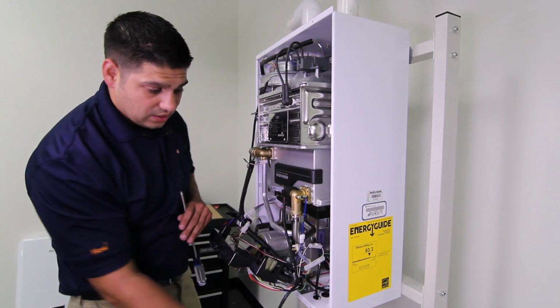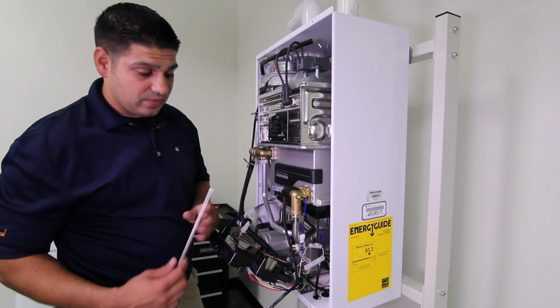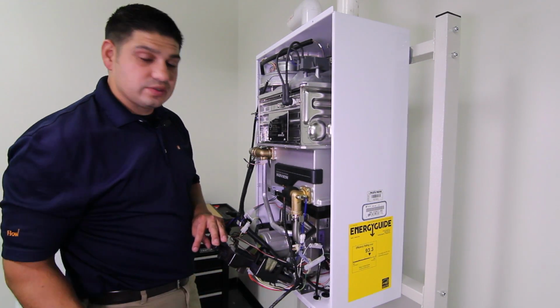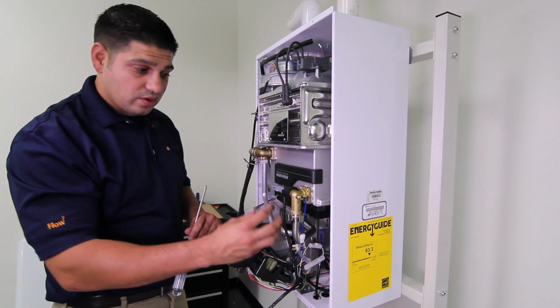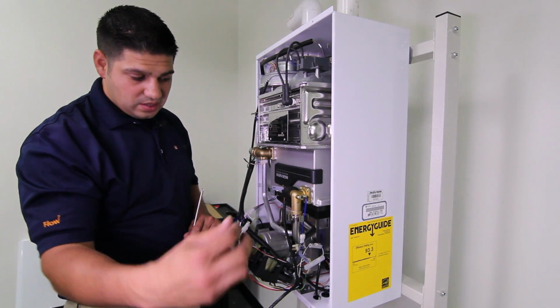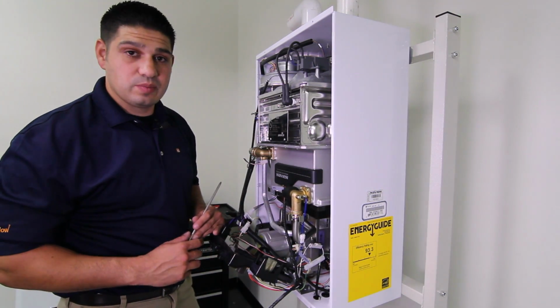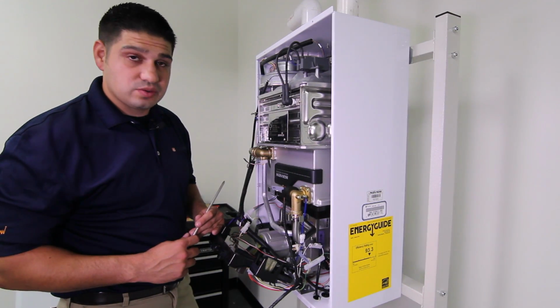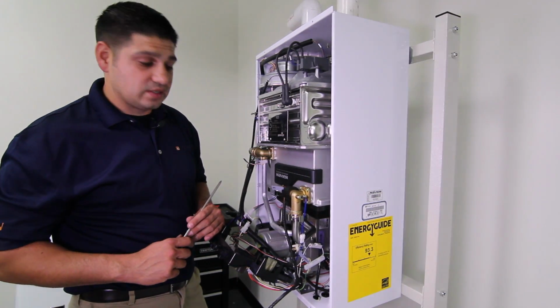Once we get that removed, there are 2 screws underneath the cabinet that secure your flow sensor to the cabinet. Once we get those off, we'll pop off your flow sensor, pop in the new one, reconnect your 2 clips, put in your 2 screws, reverse the process, and get this completed.